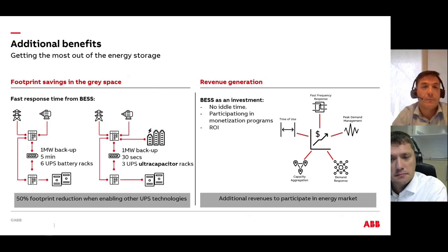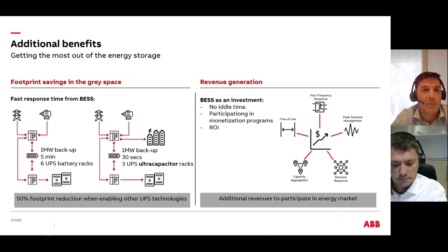At the same time, as I said, the BESS is always online. We don't have to have it offline just for backup. The lithium-ion batteries like to be cycled, which is better for the lifetime, and we can also generate revenue. The BESS is then considered as an investment. We don't have idle time, and we can participate in monetization programs like time of use, fast frequency response, peak demand management, or capacity aggregation.